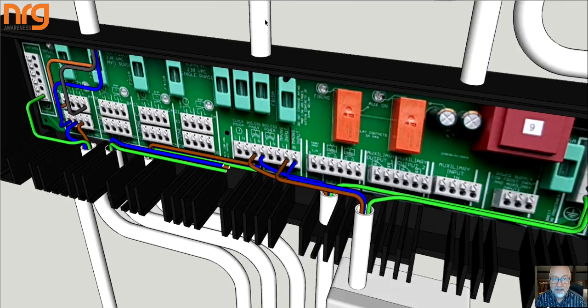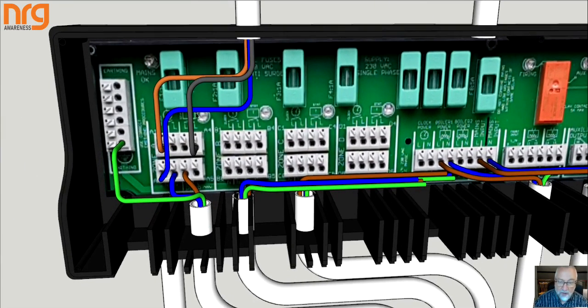And then in the meantime, if we're talking about a zone, I've said that the first zone is kind of put together, but let's look at what the blocks are doing. If we look at the block, there's A, B, and C. C1 is connected directly to that 1 amp fuse. So I can go off out to a clock, say. If I come back from my clock or programmer, I go into 2. 2 on the board is already joined to 3. If that goes out to a cylinder stat or a room stat or whatever I want, when it comes into 4, 4 has 3 jobs that it does.